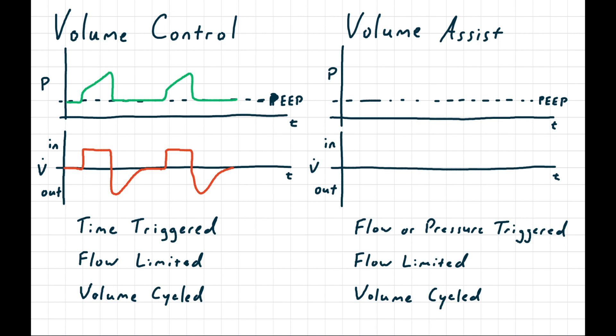The only difference between a control mode and an assist mode is how the breath is triggered. In a control mode, the breath is triggered purely by the timer set by the respiratory rate. In an assist mode, the ventilator is triggered by the patient trying to initiate a breath, and the ventilator detects that either with a flow trigger or with a pressure trigger.